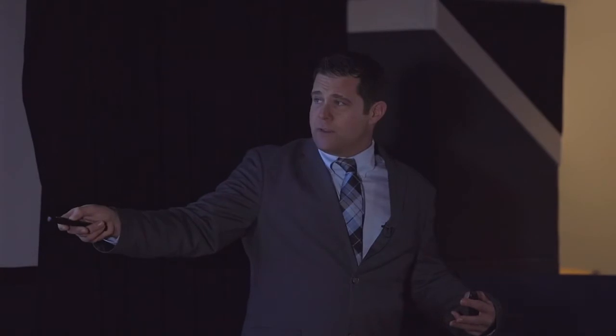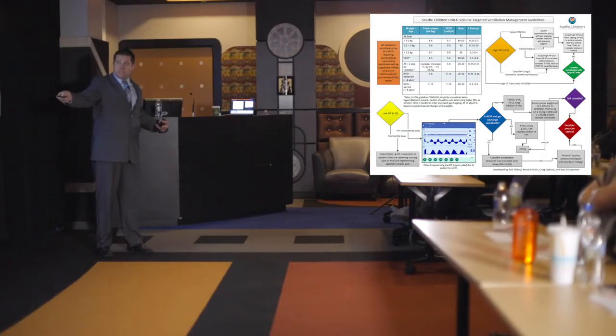And so we're using that low tidal volume, long I time, higher PIP setting. So then we have a low PIP algorithm where if their PIP's low, is it transient or is it continuous? Go back and look at your trends. And if their PIP is actually low and they don't look so good based on this, then we have a way to mitigate the issue of no pressure and no support by increasing the tidal volume target or increasing the PEEP or both. And then lastly, if they look good and they have acceptable gas exchange, rather than going into SIMV, we'll just extubate right from there if their PIPs are within a reasonable range.